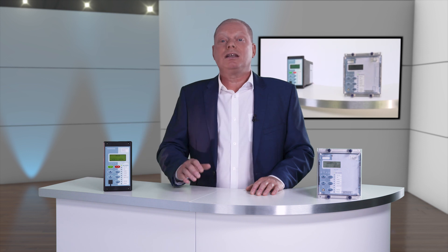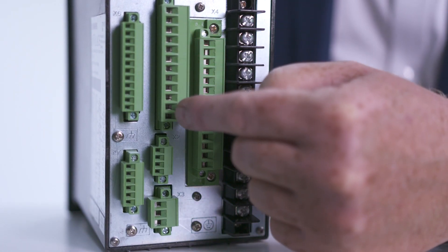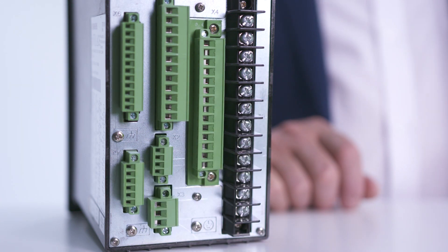Looking at the rear of the device there are terminals for current transformers, binary inputs and outputs, power supply, RS485 communication and optional temperature sensors, for example resistance temperature detectors. The 7SR 105 provides connection for four CTs providing three phase and earth fault, and can be used with a core balance CT for increased earth fault sensitivity.